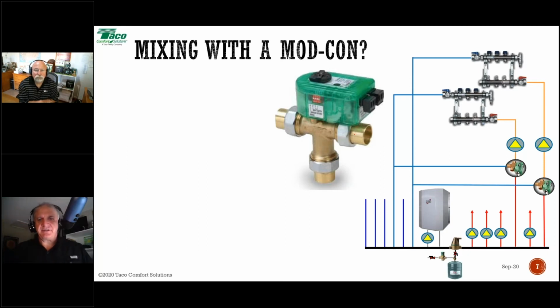I'm going to suggest to you that under those circumstances, it might behoove you to mix down the two separate radiant temperatures. So maybe I need 110-degree water in my basement slab, and maybe I need 130-degree water in my between the floor joist radiant. All right, and then I need 150-degree water for my radiators. Well, great. Set up the boiler to deliver 150-degree water. Okay, and let that thing work on its outdoor reset.